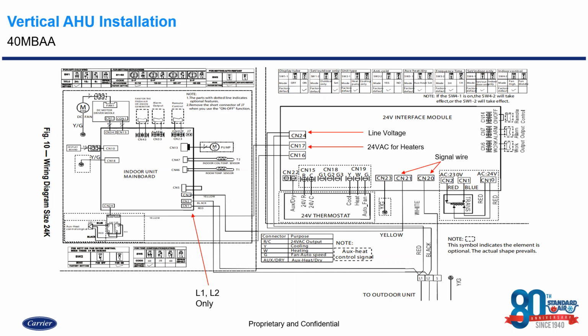Now, in these particular units, the factory set point is to have that dip switch on, which indicates we have a ductless indoor and ductless outdoor unit with a 24-volt interface. If that dip switch is in the down position or off position, that indicates we have a hybrid configuration, which means we have a ductless outdoor unit and a residential fan coil that we're trying to hook up to. So if that switch was left in the off position, then we would get a code for communication between interface to indoor unit, because the interface thinks that we're working with a hybrid scenario when in fact this is a true ductless indoor unit and we're working with a ductless indoor and a ductless outdoor.